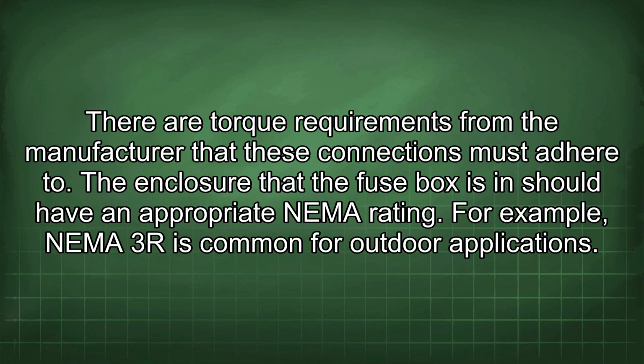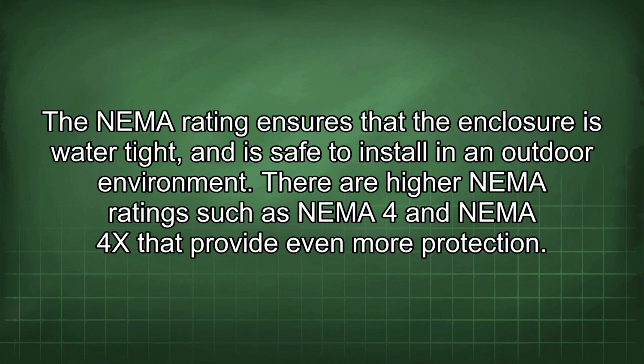The enclosure that the fuse box is in should have an appropriate NEMA rating. For example, NEMA 3R is common for outdoor applications. The NEMA rating ensures that the enclosure is watertight and is safe to install in an outdoor environment. There are higher NEMA ratings such as NEMA 4 and NEMA 4X that provide even more protection.